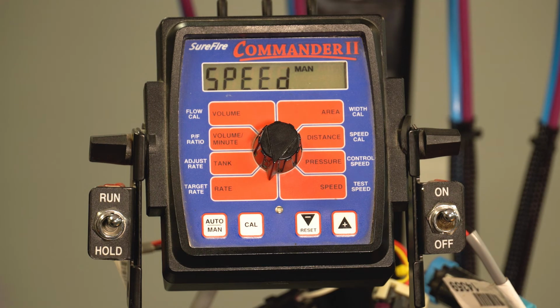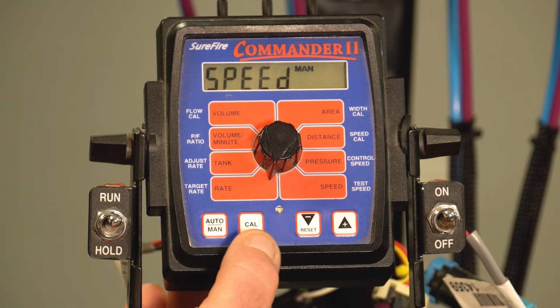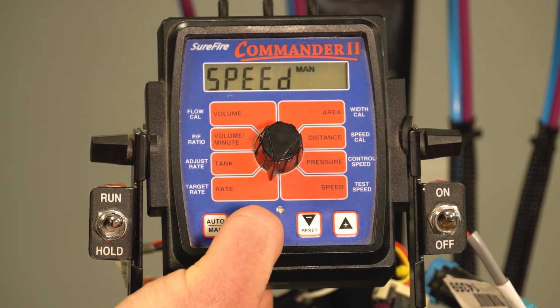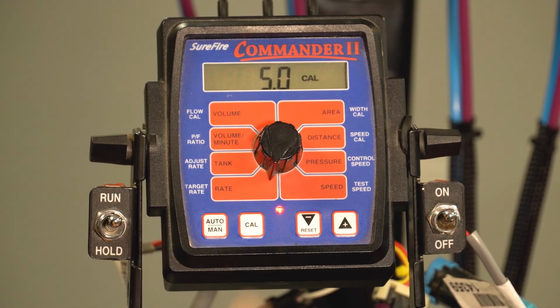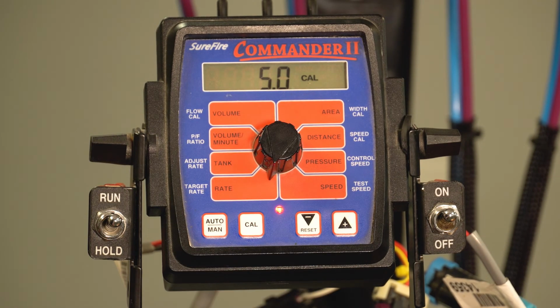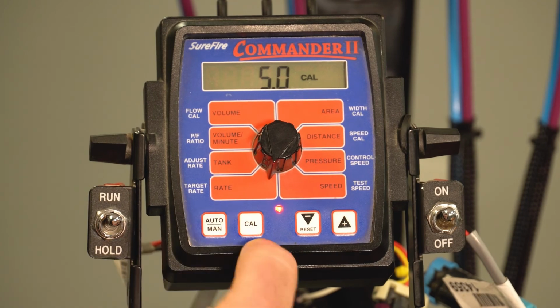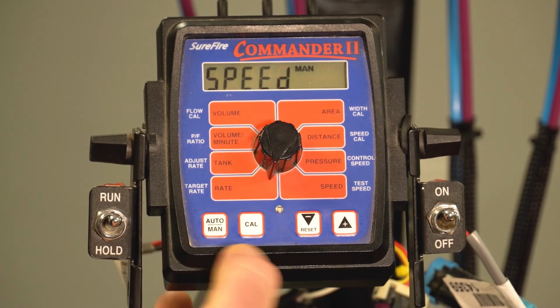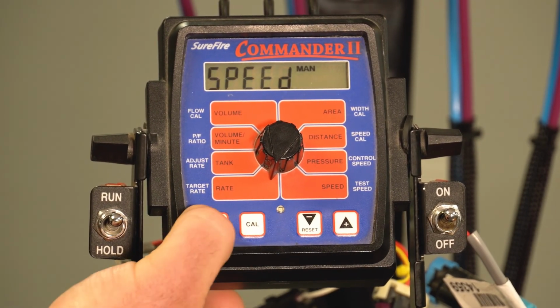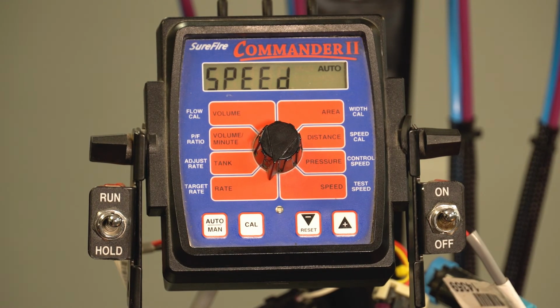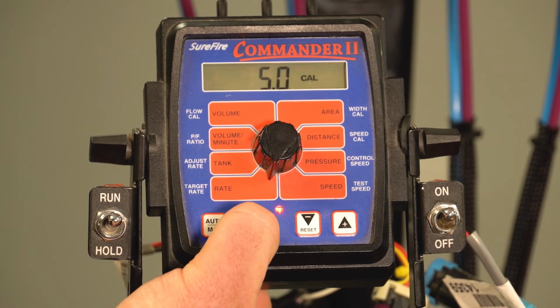So to get into the auto test, we want to go into calibration mode once again by holding down the cal button. Hold it down for a couple of seconds and then your red light will come on. We want to make sure that we're also in auto mode. So we'll jump back out really quick. I probably should have shown you that. We'll hold down the auto man button and we'll want to make sure we are in auto mode. So we're in auto mode. We'll hold the cal button back down.